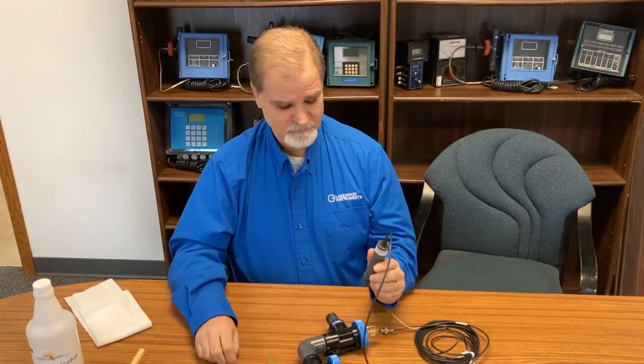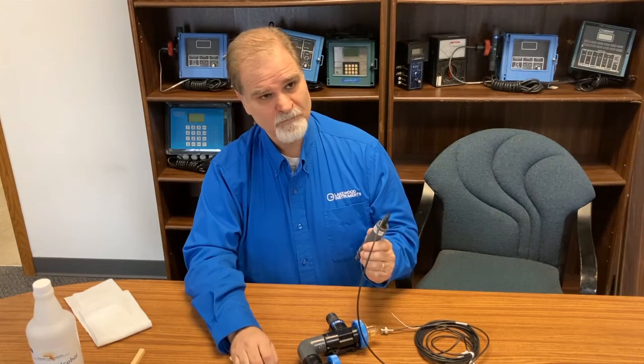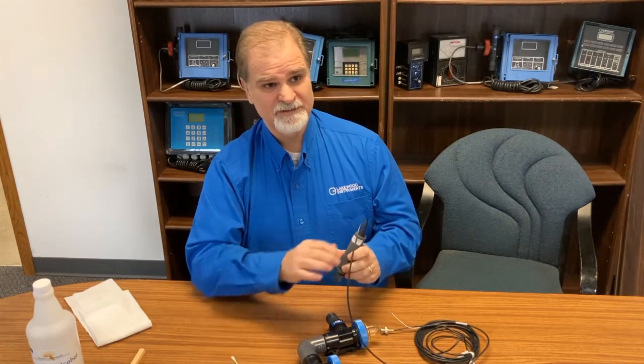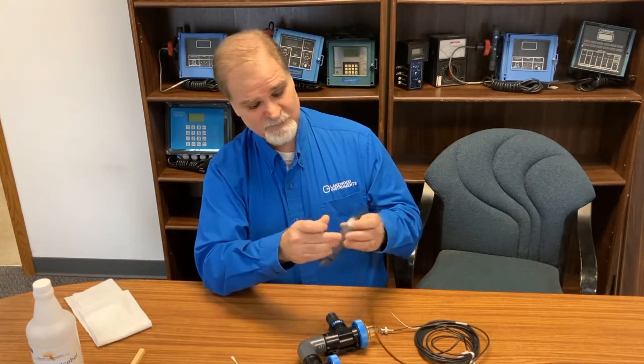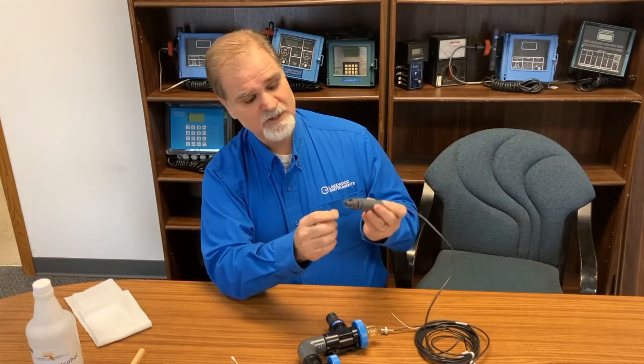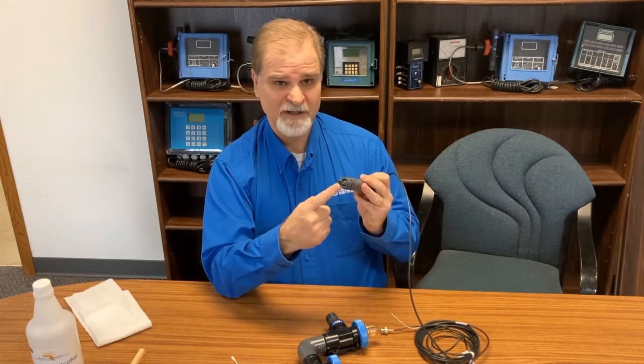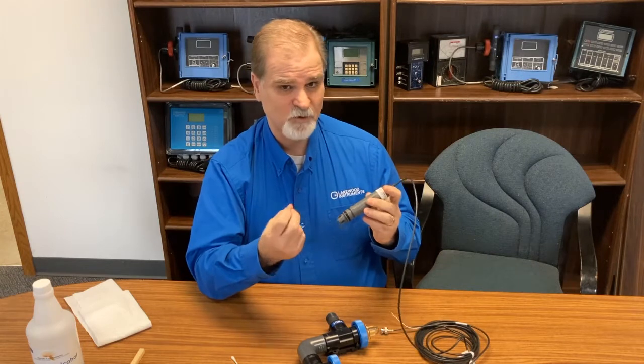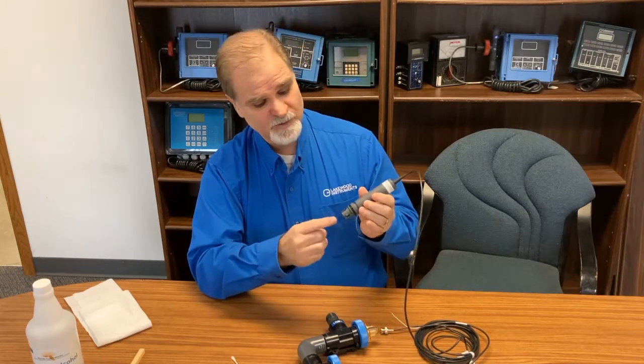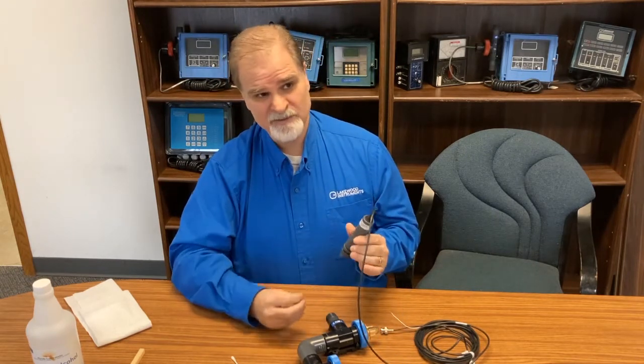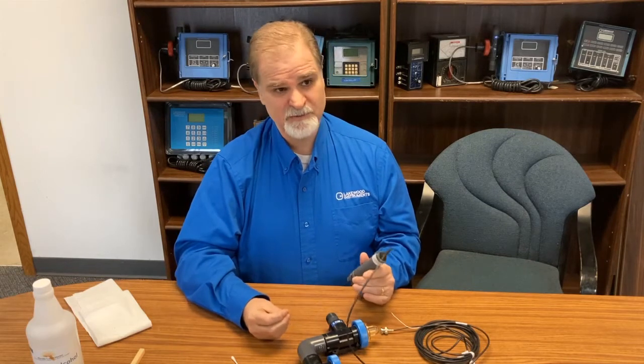Sometimes cooling towers, even in the sample lines, have debris. Talk briefly about debris. What does that do to a pH or an ORP sensor? Absolutely. That debris will impact that glass bulb and cause problems. It can damage it or break it or even remove the coating that's on that glass. We highly recommend that you use a strainer upstream of pH or ORP sensors, and don't forget to flush that strainer periodically.